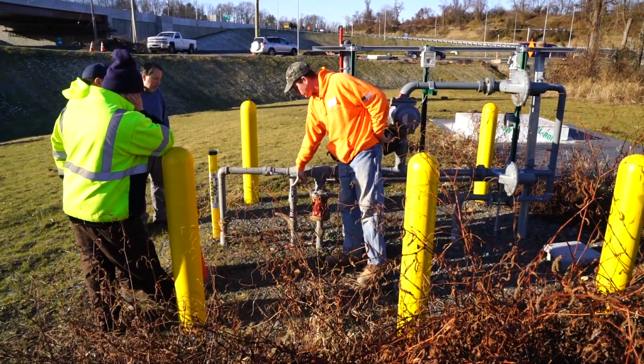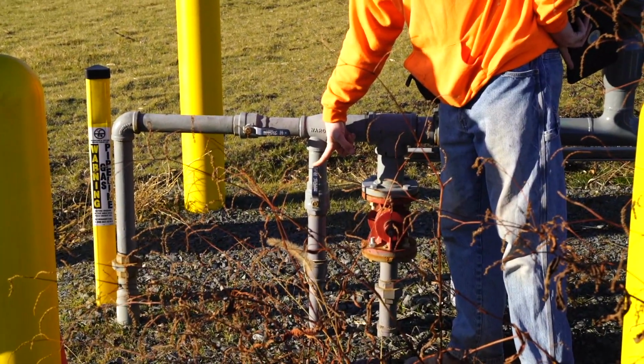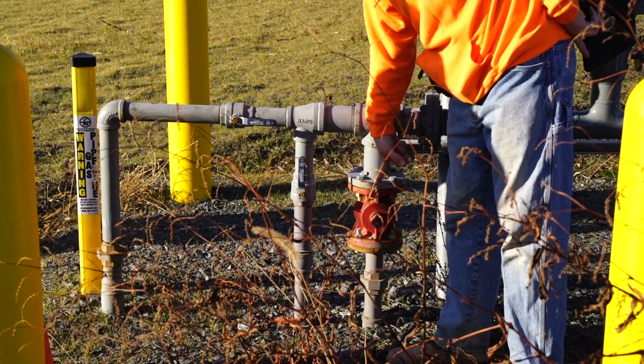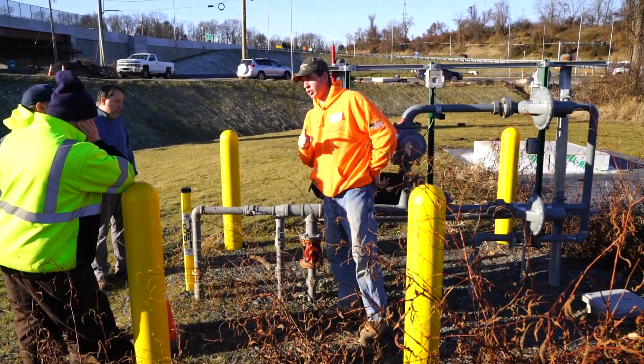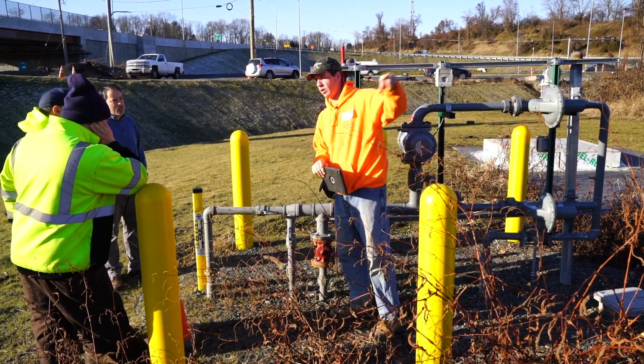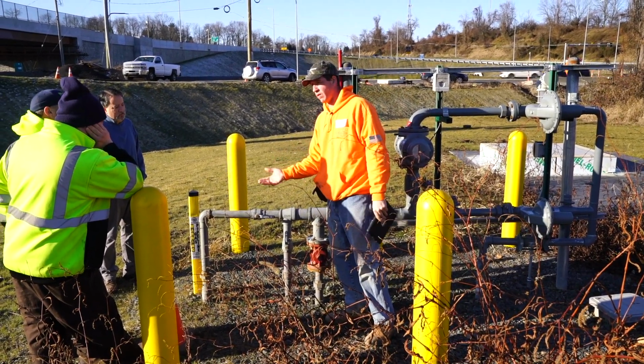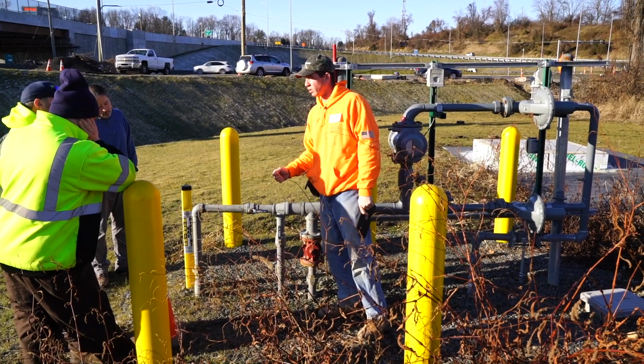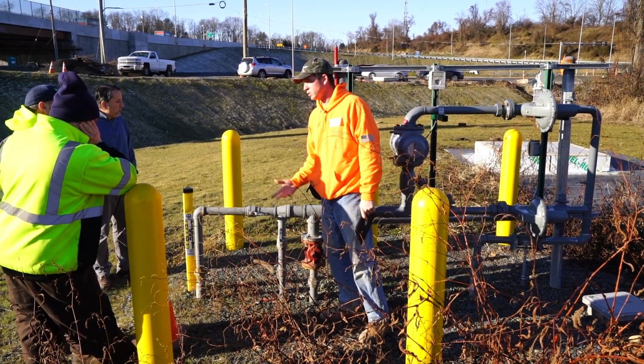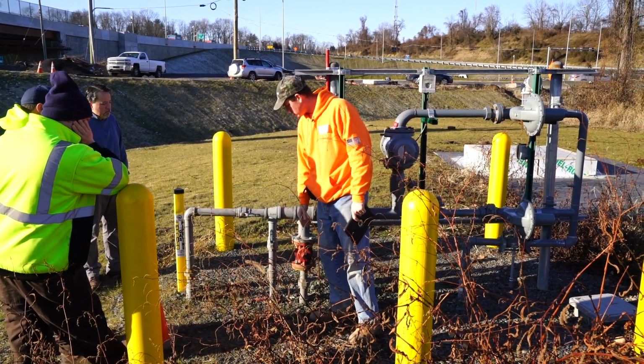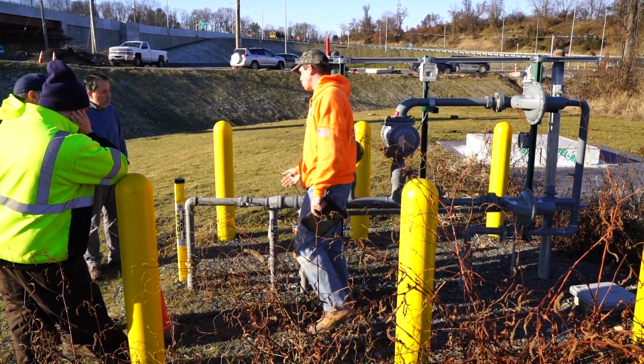This is the gas I just showed you that feeds that mechanical room for the boilers and stuff like that. This is the 2-inch line that goes to the generator. Like I said, right at the generator, like the setup I showed you out there, you have the same thing. You have a regulator, you have a valve there to shut off the generator if it ever needs to be shut off for whatever reason, serviced. All right, but these are the main ones coming off the main gas train.